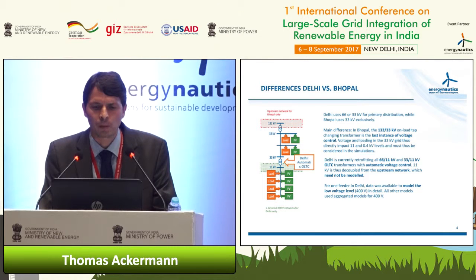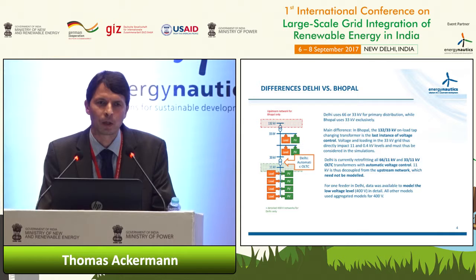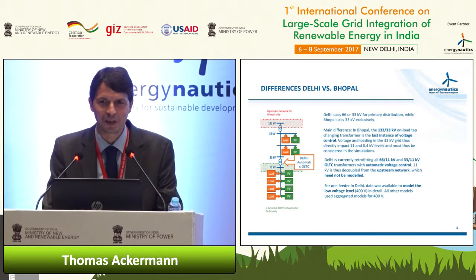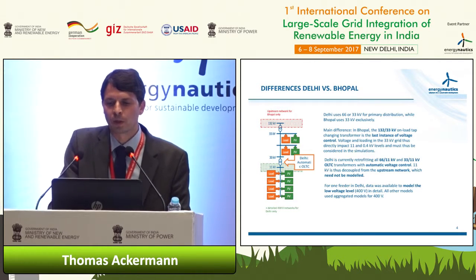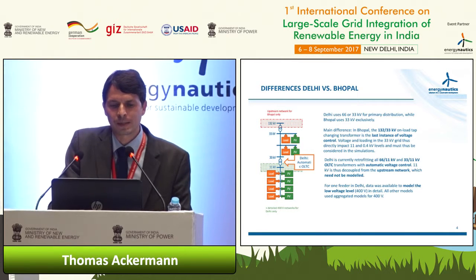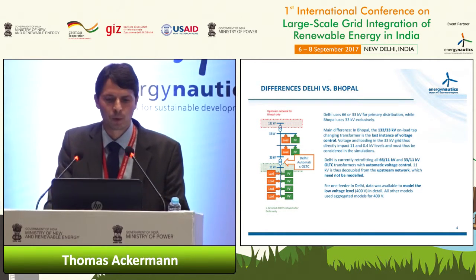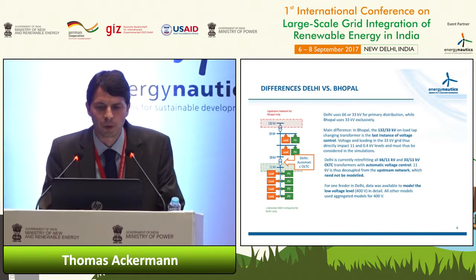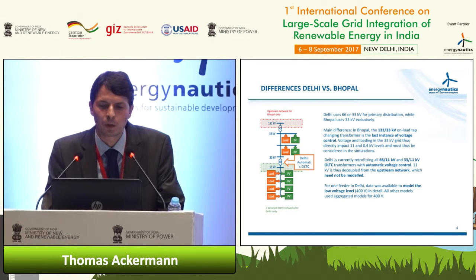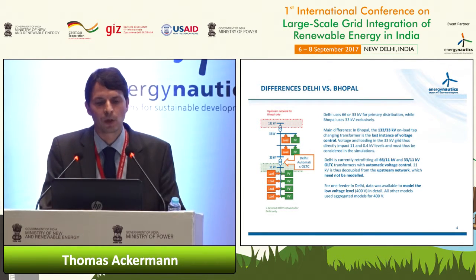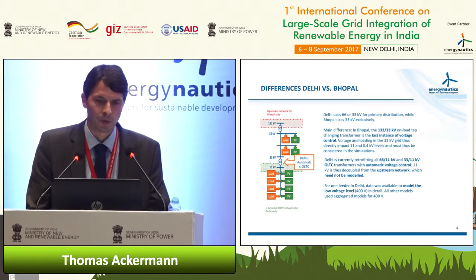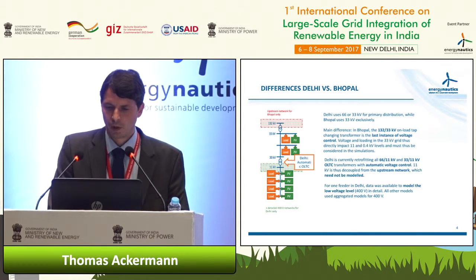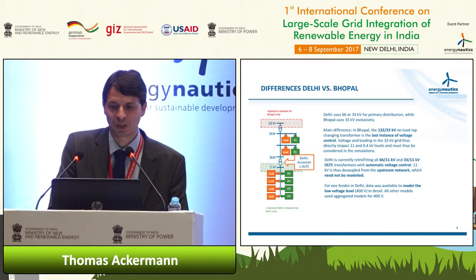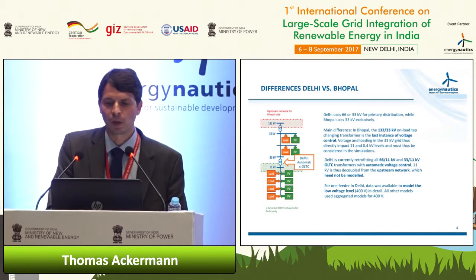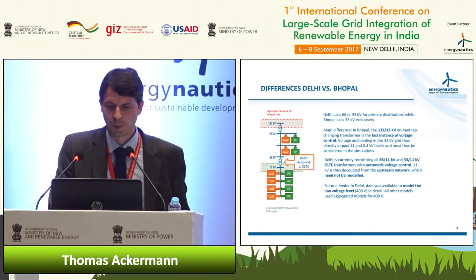Maybe first, some differences between these two. We found it's quite important to look, as mentioned earlier, voltage is a major issue besides overloading of assets. The last instance of voltage control in the Bhopal area was from the 132 to 33 kV level, whereas in Delhi it was at least currently starting from the 33 to 11 kV level. On-load tap changing is possible, though not all of it is automatic - partly it's done manually. So that's also important to notice.